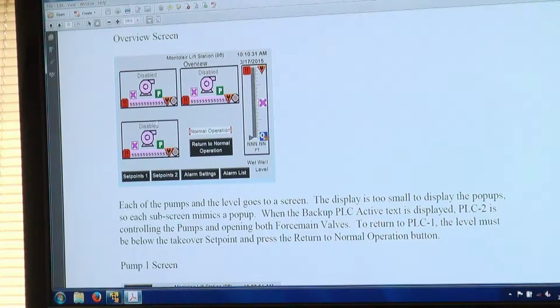But we have our 3 pumps. It goes 1, then 2, then 3. We have our level, and then we have return to normal. Normally this white text is normal operation, and you don't see this button. If PLC 2 takes over, it'll say backup control enabled. It's in red, and this button is active. That means PLC 2. To be able to return back to control, you have to go to PLC 2 and press this button. You're not able to do it from SCADA.